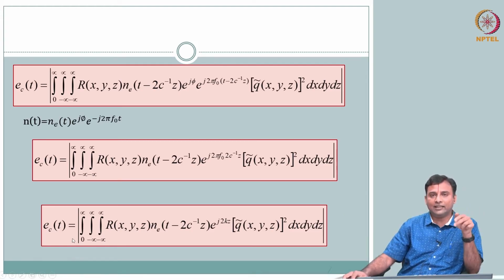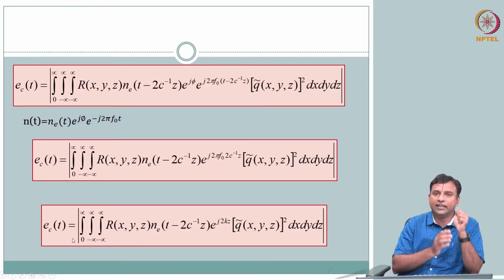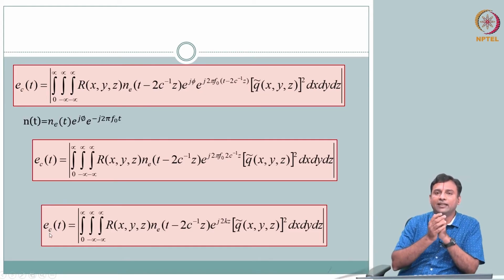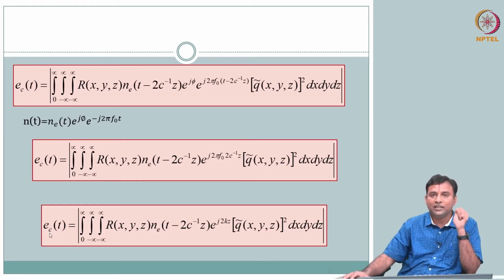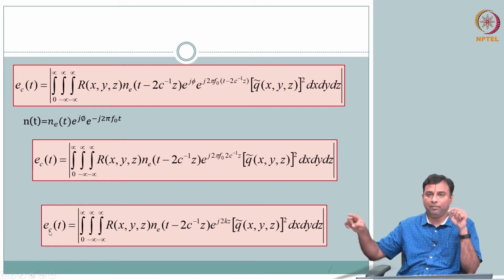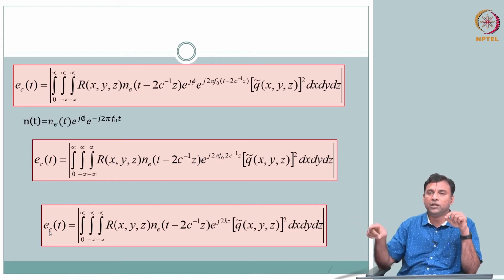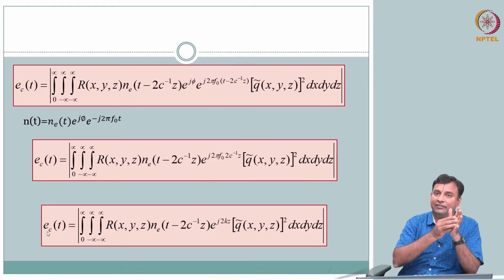But what we have not recognized so far is that the transducer is sitting at one location, right? We have not really talked about that. We have just said this is the echo received by the transducer as a function of t. But if you want to scan, then you need to have x, y, z. You get only z here. The echo is a function of time, which probably is related to the depth, which we will finalize now. But the idea is we don't have a location for where the transducer is sitting, because that's where the pulse is sent and received.